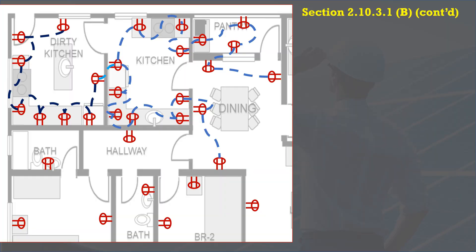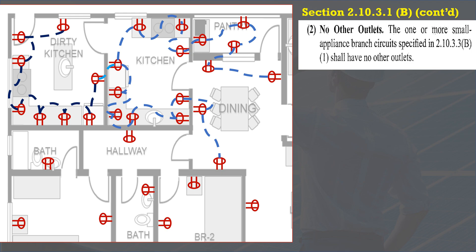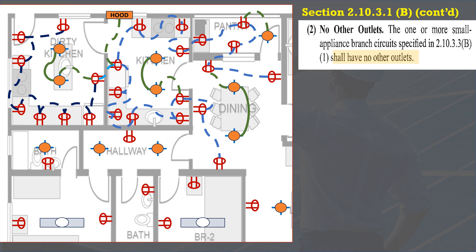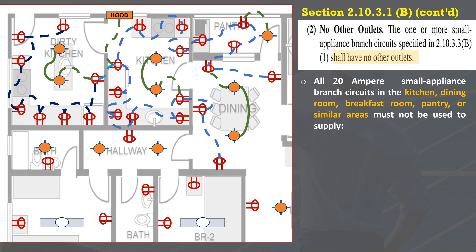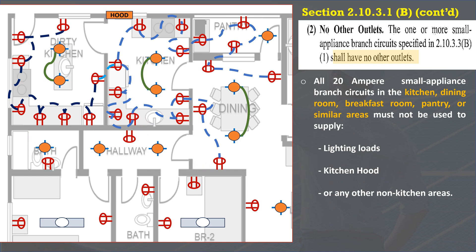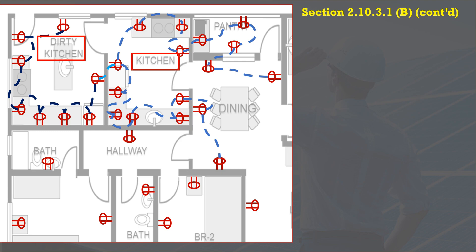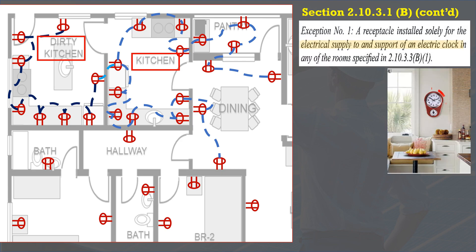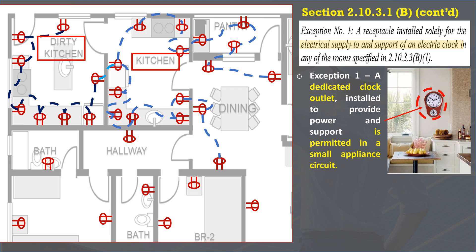In paragraph 2 of Section 2.10.3.1B, No Other Outlets: the one or more small appliance branch circuits specified in 2.10.3.3B.1 shall have no other outlets. Hence, all 20A small appliance branch circuits in the kitchen, dining room, breakfast room, pantry, or similar areas must not be used to supply lighting loads, kitchen hoods, or any other non-kitchen areas. A receptacle outlet for a dedicated clock installed in the kitchen, dining room, breakfast room, pantry, or similar areas is permitted in a small appliance circuit as specified in Exception 1.